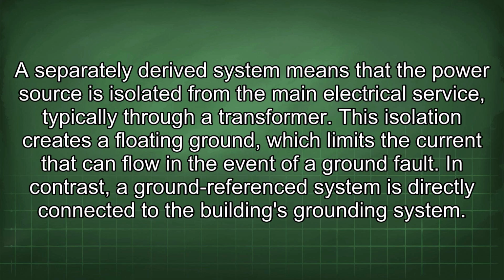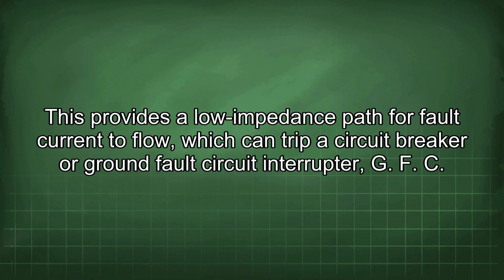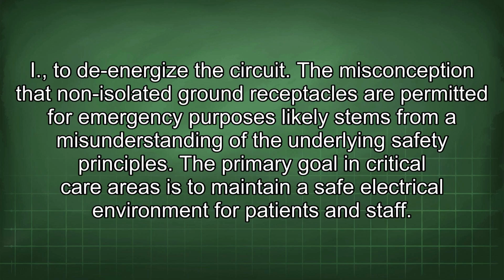A separately derived system means that the power source is isolated from the main electrical service, typically through a transformer. This isolation creates a floating ground, which limits the current that can flow in the event of a ground fault. In contrast, a ground-referenced system is directly connected to the building's grounding system. This provides a low impedance path for fault current to flow, which can trip a circuit breaker or ground fault circuit interrupter (GFCI) to de-energize the circuit.